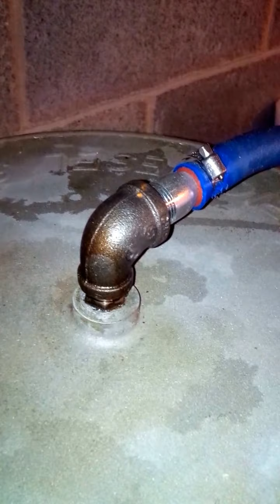Now over here, this is the drop down tube. I'm not going to pull it out right now because it is running. It's dropping the hot oil into the center of the top of the centrifuge, where it slowly makes its way down the side, and then it slowly creeps up onto the vertical side of the centrifuge. At that point it is spun at approximately 3,400 RPM.